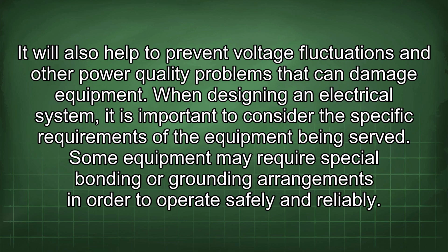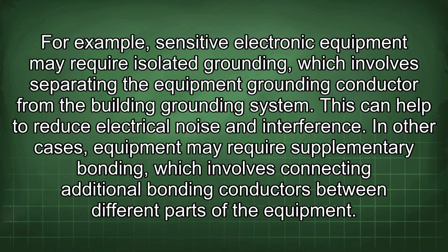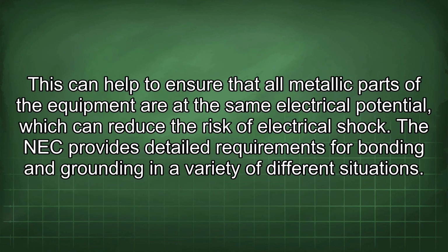When designing an electrical system, it is important to consider the specific requirements of the equipment being served. Some equipment may require special bonding or grounding arrangements in order to operate safely and reliably. For example, sensitive electronic equipment may require isolated grounding, which involves separating the equipment grounding conductor from the building grounding system. This can help to reduce electrical noise and interference. In other cases, equipment may require supplementary bonding, which involves connecting additional bonding conductors between different parts of the equipment. This can help to ensure that all metallic parts of the equipment are at the same electrical potential, which can reduce the risk of electrical shock.